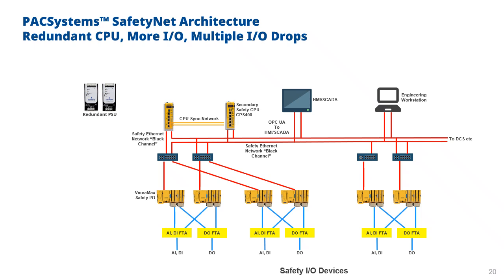The I/O limitation for the SafetyNet system is 2000 I/O maximum, or actually that's 1200 analog in, or 2560 digital in and 2560 digital out. That would be quite a large system by safety standards, but that's quite a large system itself. But if you wanted to, you could go to a larger system by having multiple safety systems together.